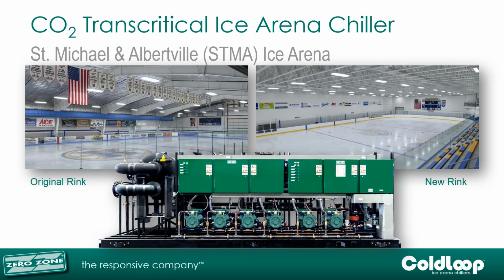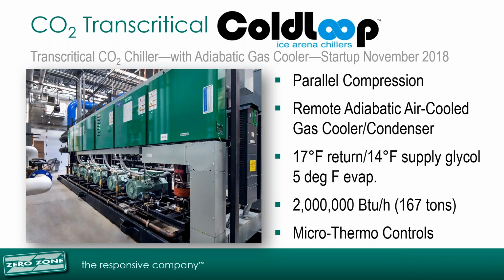ZeroZone worked closely with the stakeholders to develop a transcritical CO2 solution that would fit their needs for the next 30 years. The chiller package was an indirect system where CO2 cooled the glycol, and the glycol is pumped to the floor to refrigerate the ice. It's similar in design to the supermarket in Vermont that I covered earlier. The system has 4 Bitzer reciprocating compressors for chilling the glycol and 2 Bitzer compressors for parallel compression to remove the flash gas from the flash gas receiver. The system utilized Micro-Thermo Controls.